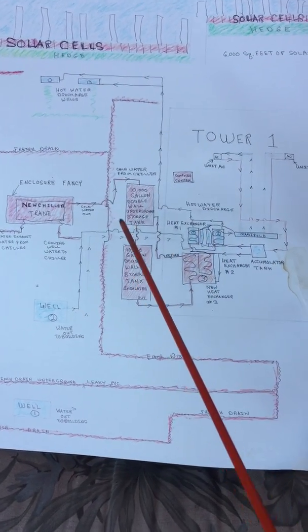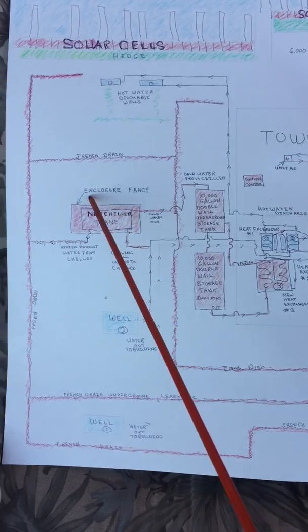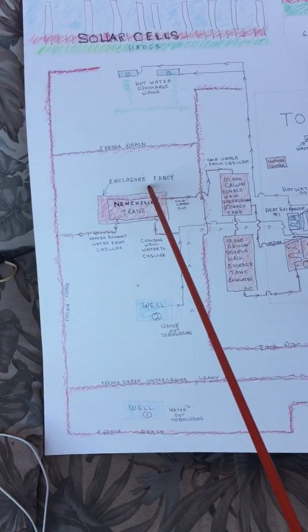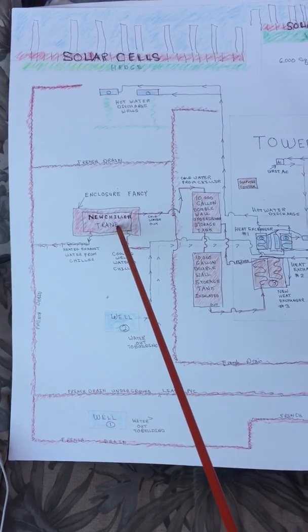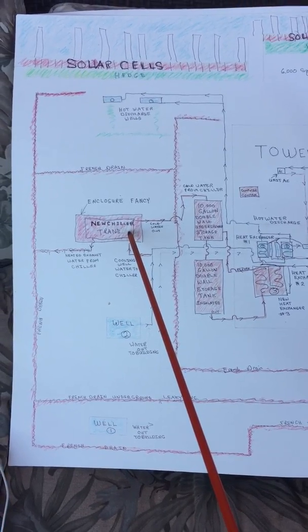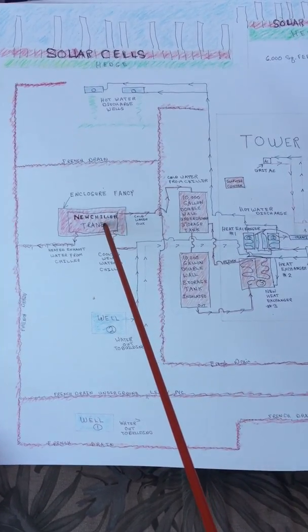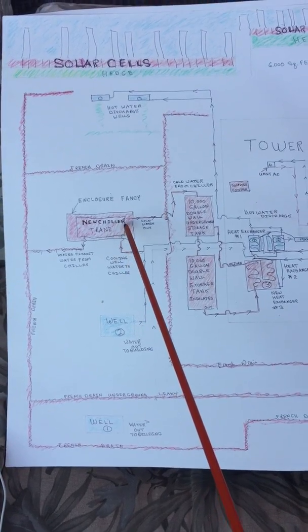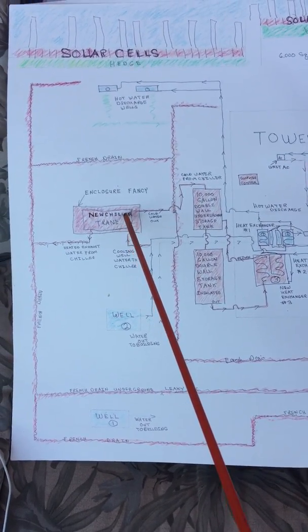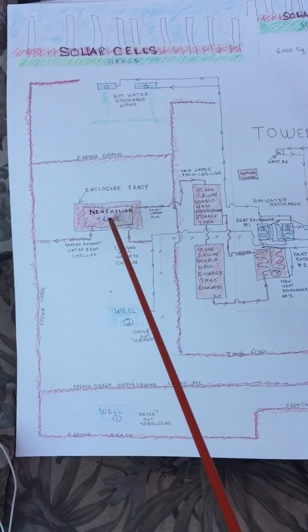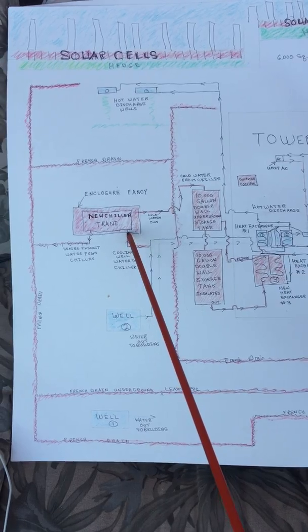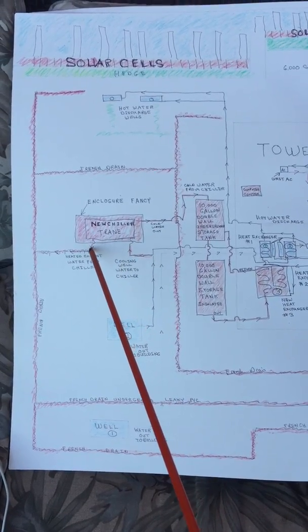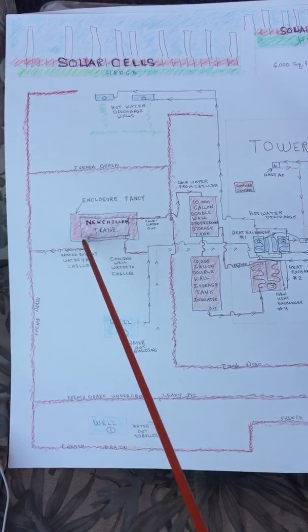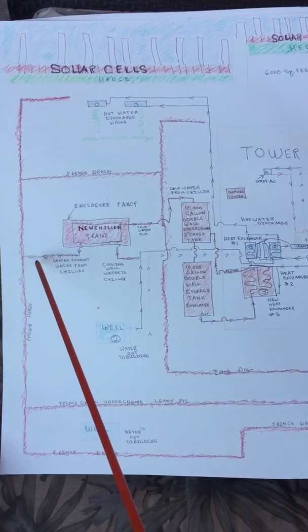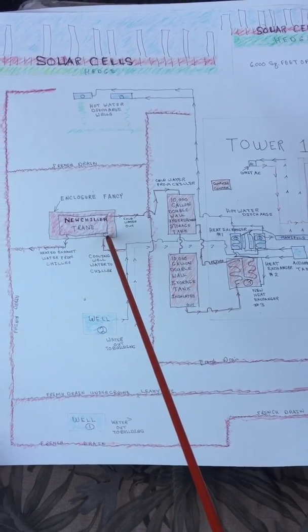Now, how do we get the water to put into these tanks? We buy a new Trane chiller system like they have at 90 Edgewater, but theirs are from 1987, and they're still working great according to Aaron Glasser, the president. Except theirs works a little different. They have a water-cooled chiller, an air-cooled chiller with a cooling tower on the roof. We have the well, so we can supply cooling water to keep the chiller from overheating, and that well water goes into the French drains and drains back into the ground. It doesn't cost us anything.